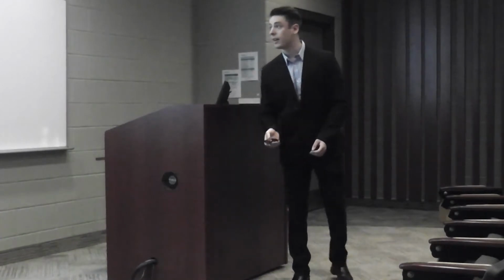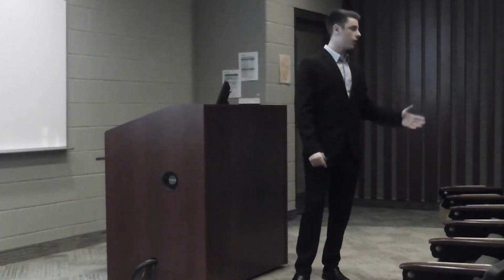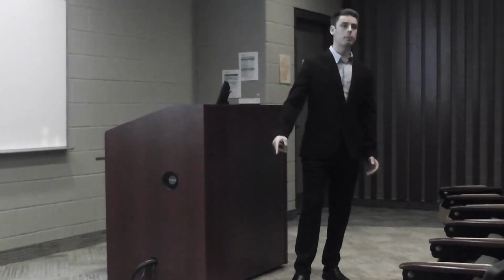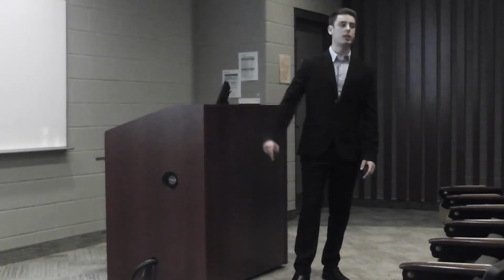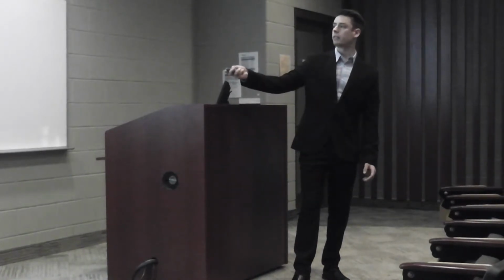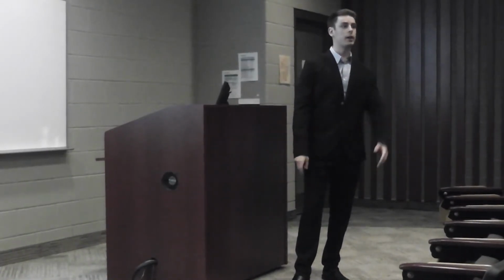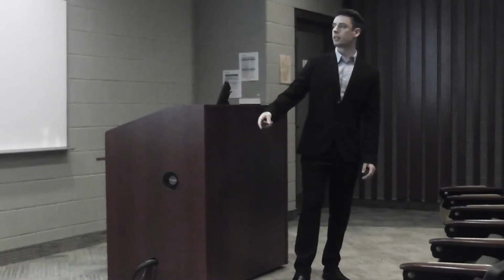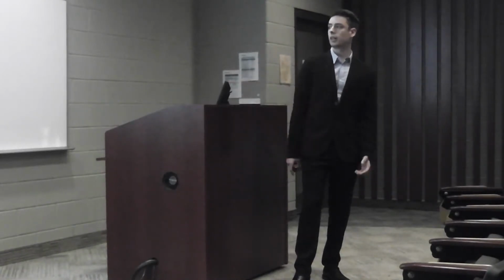So the conditions that we're under in the laboratory: it's occupied from 8 a.m. to 10 p.m. All equipment and materials testing is going to be active. Ventilation that Miles determined would be 305 CFM in his ARP. And the outdoor design temperature is 86 and indoor 75.